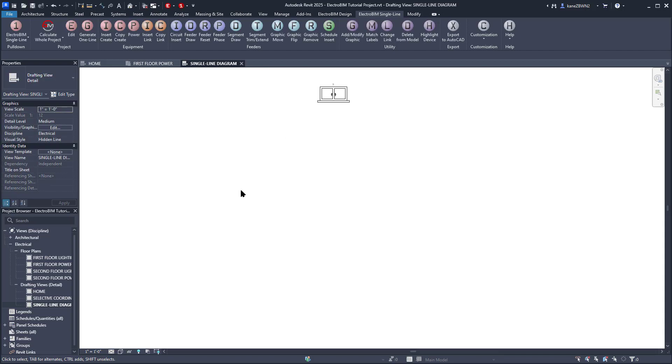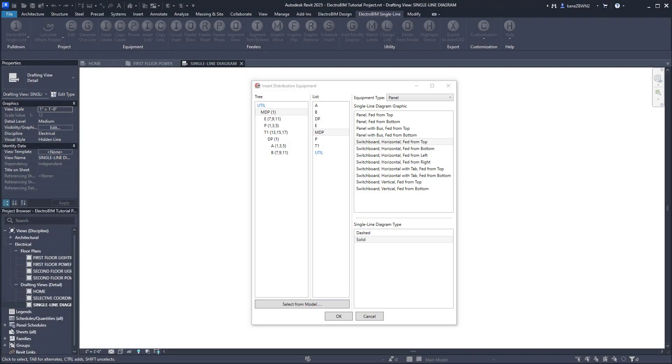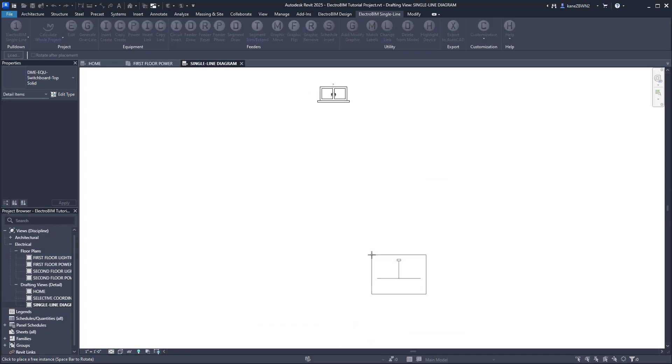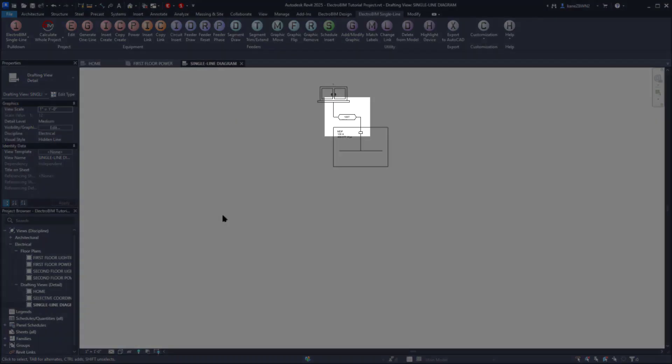We'll run Insert Link again and select the next device down, MDP. Because this device has multiple downstream connections, and because of some default Electro BIM customization settings, it goes with the Switchboard Horizontal Fed From Top graphic. We'll stick with that. Press OK and specify a point underneath the transformer, where it will insert the graphic and labels. Electro BIM will also detect any connected devices on the single line and draw the feeders automatically.